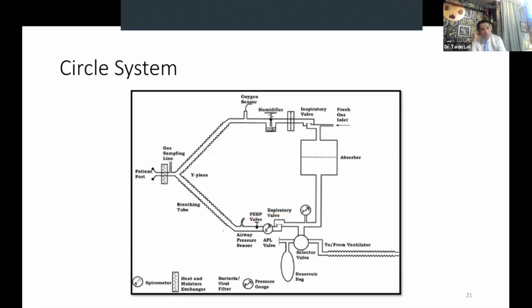Then on the expiratory side, we have the airway pressure sensor, the PEEP valve, then the expiratory unidirectional valve, and finally your selector, that is your bag ventilator selector switch. On one side of the selector switch is your bag, and on the other, your ventilator. Further, gases go to your carbon dioxide absorber and then again mix with your fresh gas flows. That is how the circle system is designed.